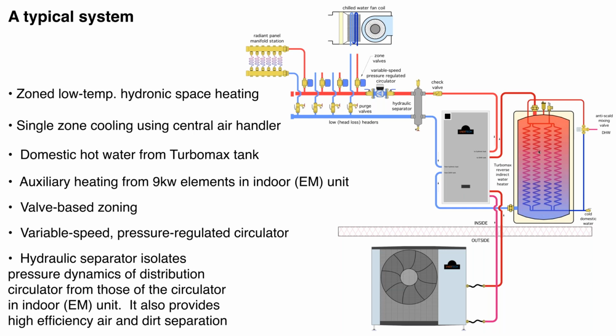And I do want to stress that TurboMax tank was not an arbitrary decision. That was a product that was well matched to the performance of the heat pump. The idea being to minimize the temperature difference between the water that the heat pump is heating, which would be in the shell of this tank, and the temperature of the domestic water. The more heat exchange area we have in that tank, the lower we can operate the heat pump and still get adequate domestic hot water delivery temperature. And then the final component over here, this is an anti-scald mixing valve. I would certainly recommend you do that on any water heater, regardless of what the heat source is.